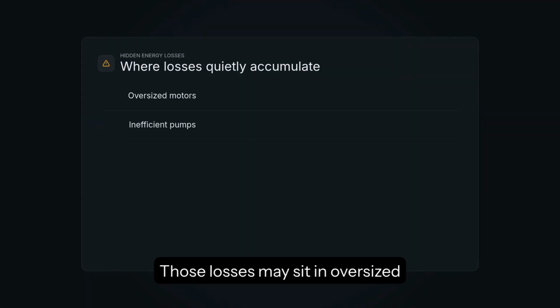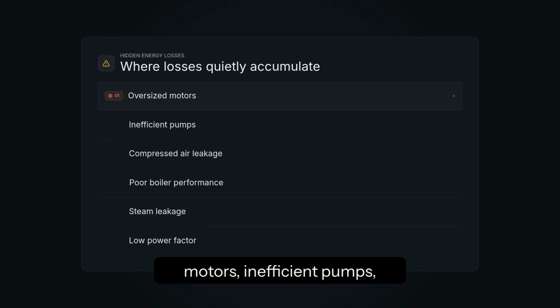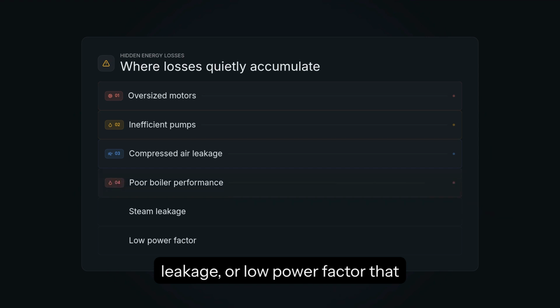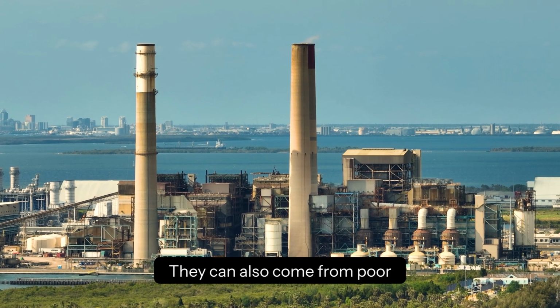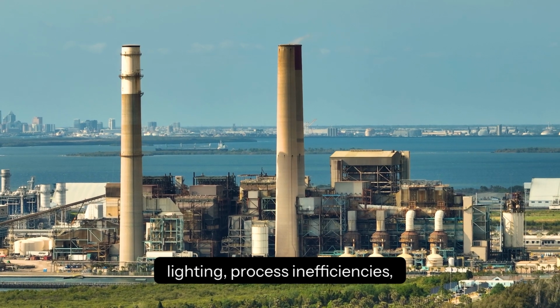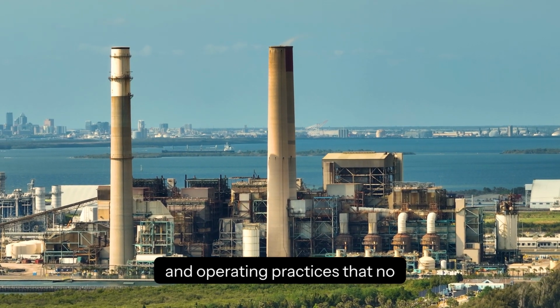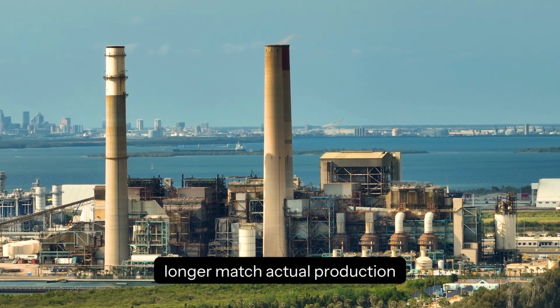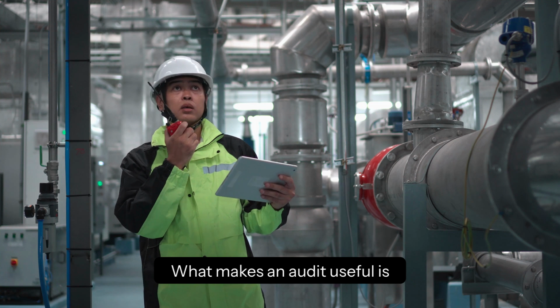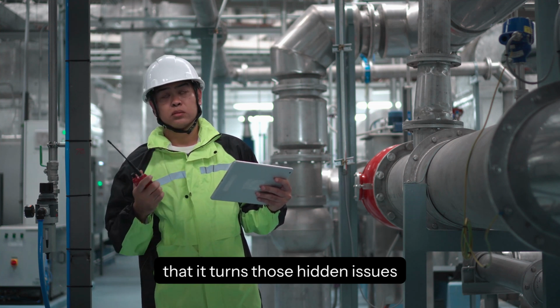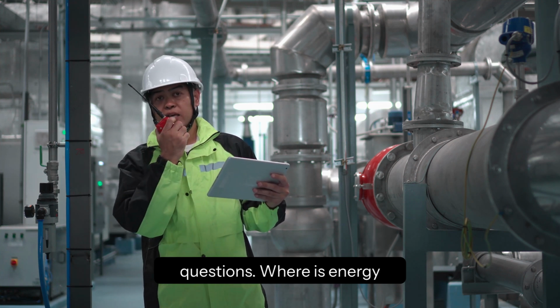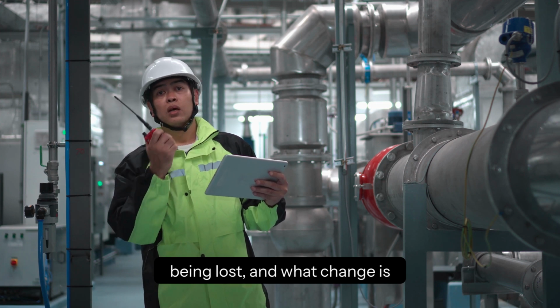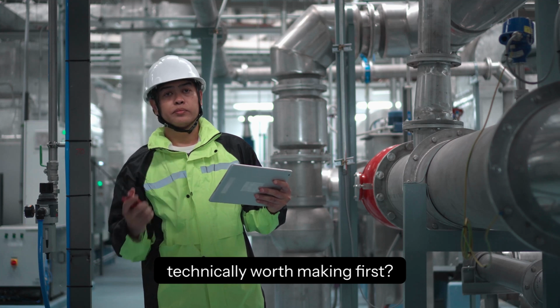Those losses may sit in oversized motors, inefficient pumps, compressed air leakage, poor boiler performance, steam leakage, or low power factor that quietly pushes cost upward. They can also come from poor load management, outdated lighting, process inefficiencies, and operating practices that no longer match actual production needs. What makes an audit useful is that it turns those hidden issues into visible engineering questions. Where is energy being lost, and what change is technically worth making first?